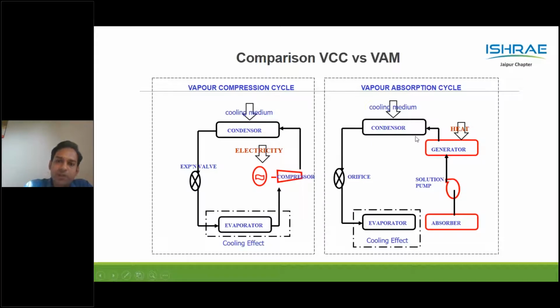Whereas in the absorber side you can see the rest of the components are quite same, that is evaporator, condenser, we have the orifice, only the compressor part is not there, so hence there is no electrical consumption in vapor absorption machines. The compressor's function is done by components we will discuss: an absorber, a solution pump, and a generator.